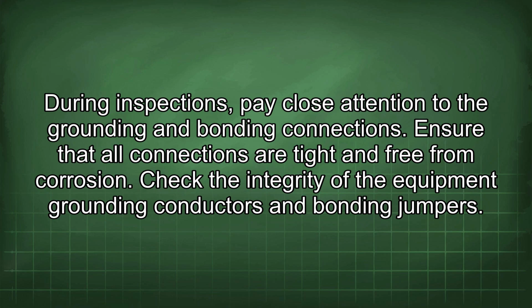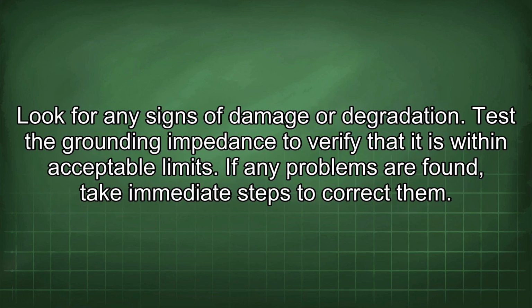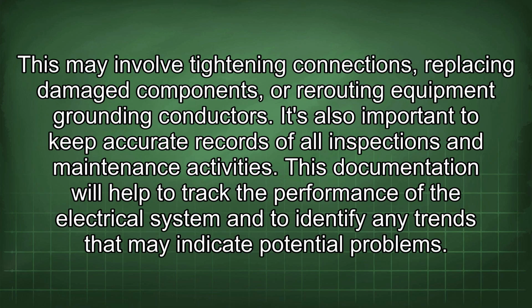Ensure that all connections are tight and free from corrosion. Check the integrity of the equipment grounding conductors and bonding jumpers. Look for any signs of damage or degradation. Test the grounding impedance to verify that it is within acceptable limits. If any problems are found, take immediate steps to correct them. This may involve tightening connections, replacing damaged components, or rerouting equipment grounding conductors.